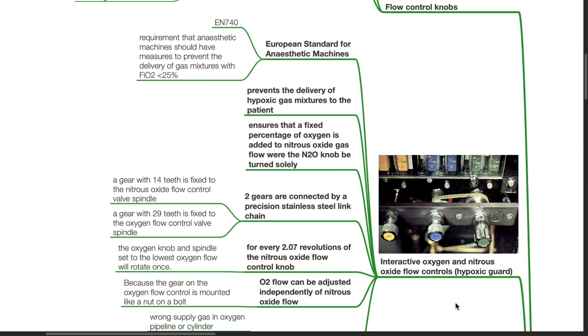It ensures that a fixed percentage of oxygen is added to nitrous oxide gas flow where the nitrous oxide knob be turned solely. Two gears are connected by a precision stainless steel link chain. A gear with 14 teeth is fixed to the nitrous oxide flow control valve spindle and a gear with 29 teeth is fixed to the oxygen flow control valve spindle. For every 2.07 revolutions of nitrous oxide flow control knob, the oxygen knob and spindle set to the lowest oxygen flow will rotate once.